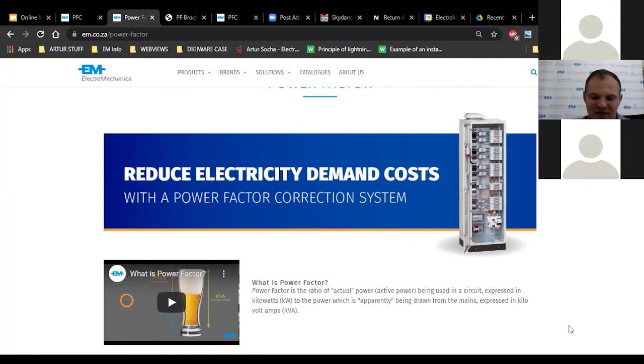But I can use the example again with the gensets. Customer has only got gensets. He's got a solar plant and he's got a lot of drives, and now nothing wants to work. His generator doesn't want to sync properly. The PV keeps disconnecting, but the guy that did the VSDs is happy because he sold a lot of VSDs and everything is working. But now he's created this other problem. Now what you need to do is get to those drives. Do they have line reactors? Do they have chokes? Do they have front ends? Or do they have nothing? Then you've got to say, okay, we need to look at active filtering at the point of coupling to those drives. And that may be enough to lower the harmonics to make the solar system work fine, with no issues with the generator. There's not an answer that I can tell you which is best at this stage. You have to do a log to see.